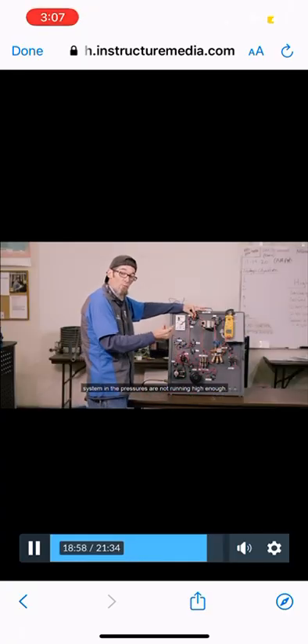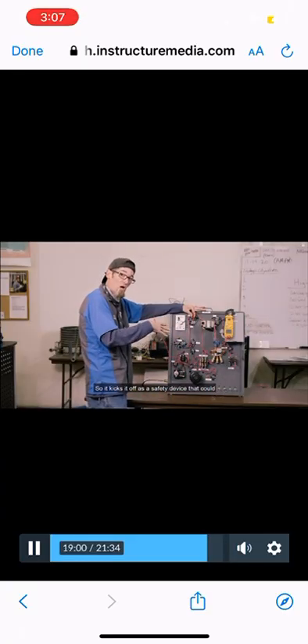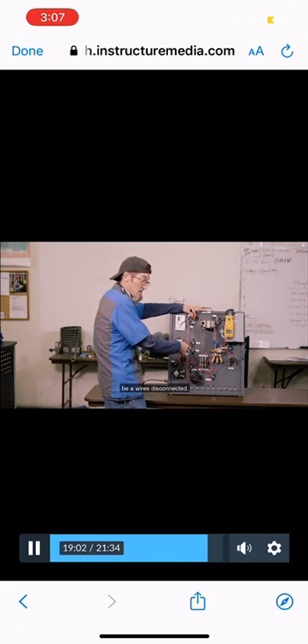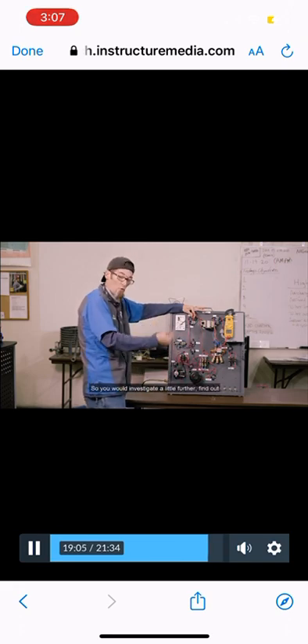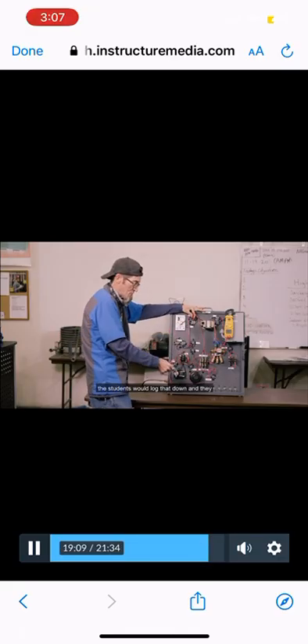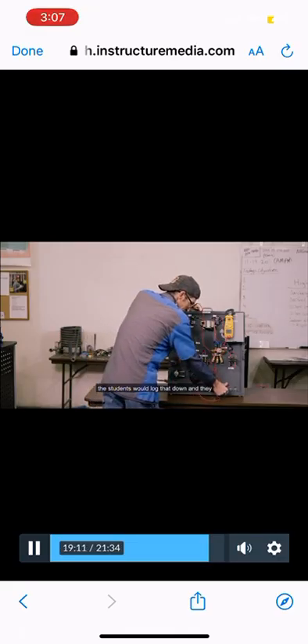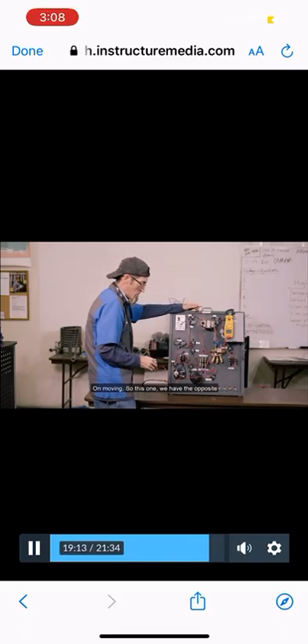What that means is this low pressure switch is going to be open. So that could be that there's a leak in the system and the pressures are not running high enough, so it kicks it off as a safety device. That could be a wire's disconnected, could be just pulled out of the connector. So you would investigate a little further, find out what's going on with that pressure switch. The students would log that down and they would keep on moving.